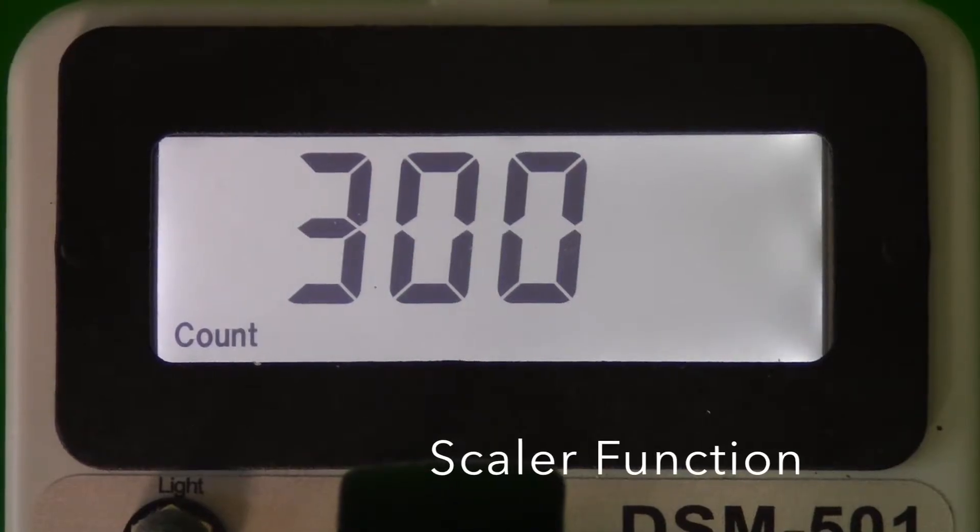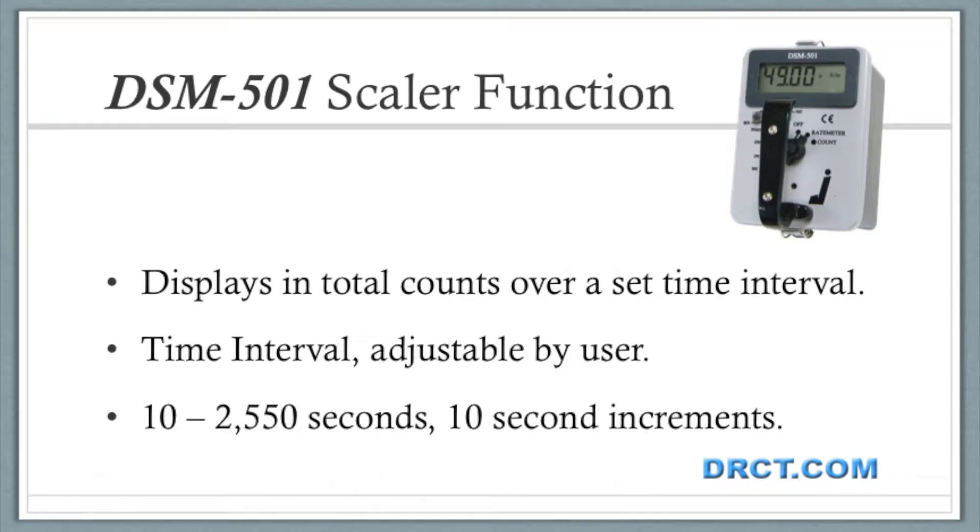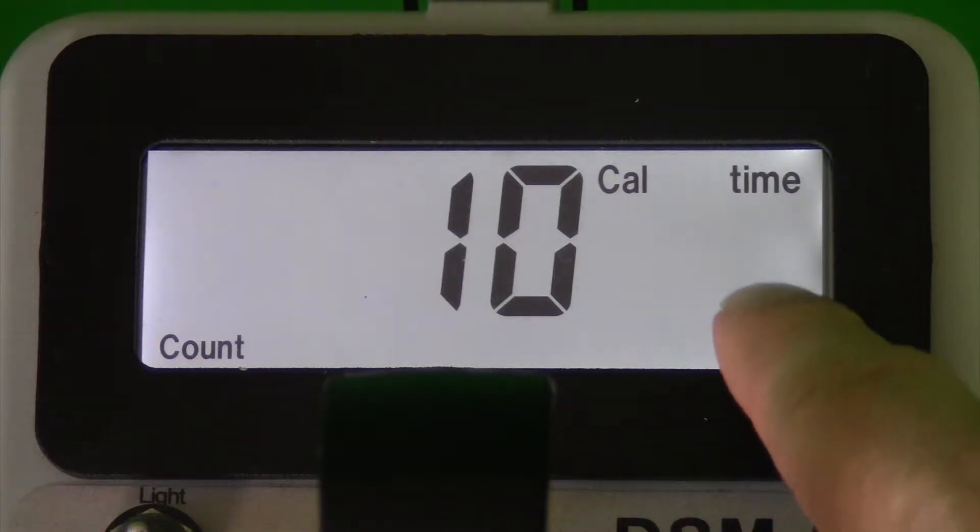The scalar mode displays and counts total counts over a set time interval. The interval is adjustable by the user, with counting times from 10 to 2,550 seconds in 10-second increments. The scalar is now set at a 10-second count interval for demonstration purposes.